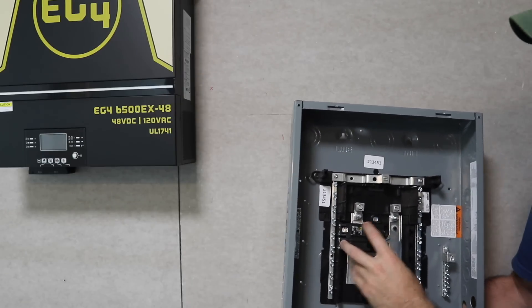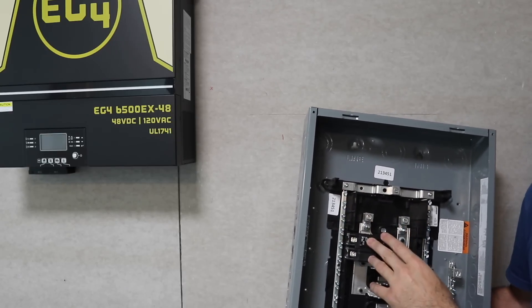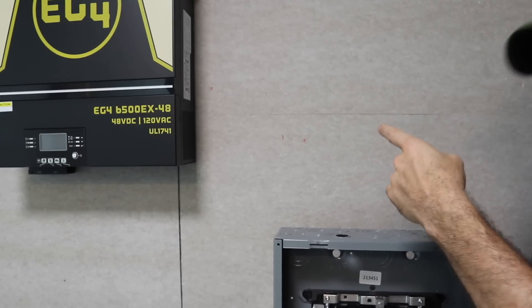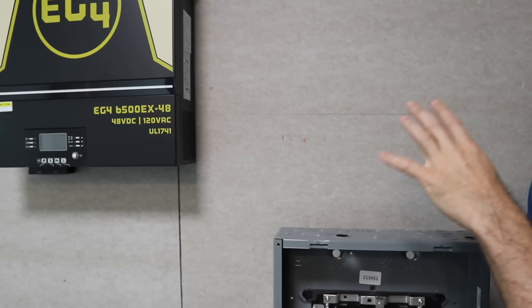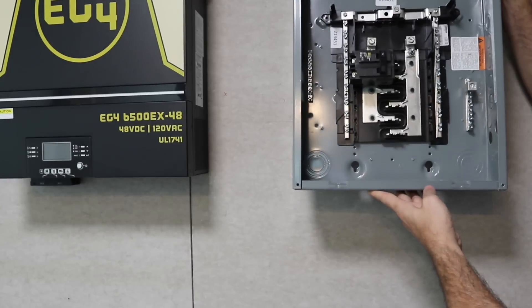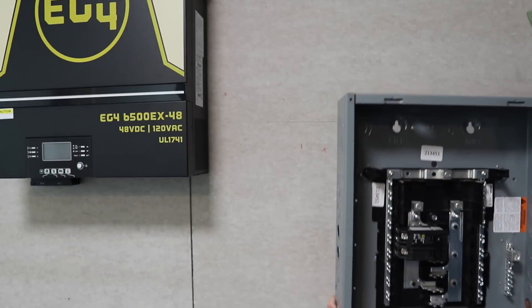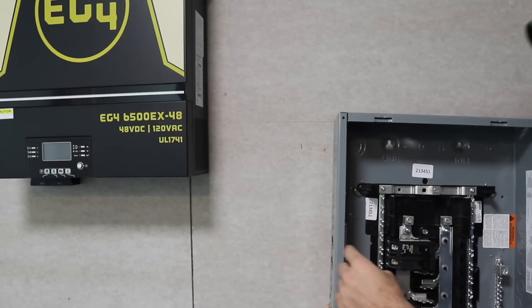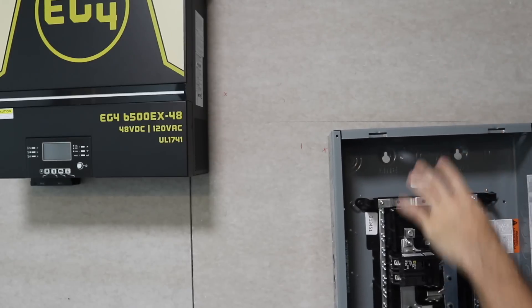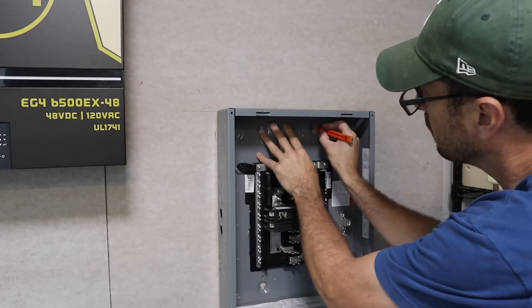The way my system is set up, I have a sub panel next to my inverters. I'm going to land line one and line two onto the 70 amp breaker, then take that back through a safety switch to my main panel where I have another 70 amp breaker. With that 70 amp breaker I've got a generator interlock kit — it runs just like a generator, same as my old Growatt system. I'm mounting the sub panel a bit lower for better access, and I've got two knockouts on the side ready to receive those lines from the inverters.